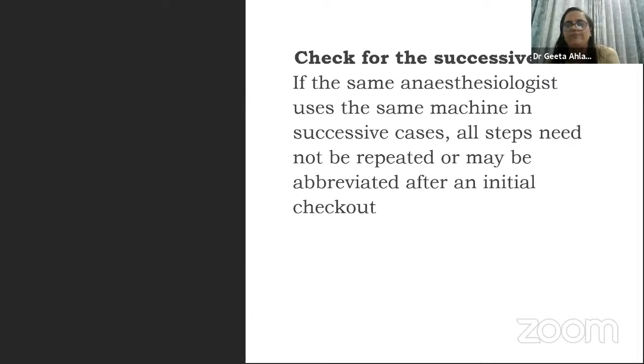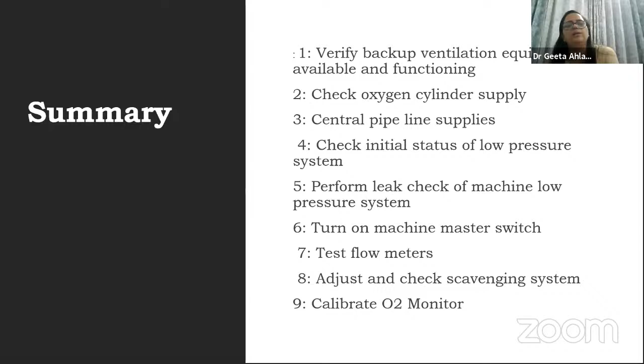Just to summarize, please verify your backup ventilation equipment. It should be available and functioning. Check all your supplies, check the initial status, check all leak tests, all your switches, all your flow meters, scavenging systems, and calibrate all your monitors. Safety is prime, safety saves us, but a small reminder to all: all this is useful like a parachute. A parachute is useful only if it is open. If you jump with a closed parachute, it is as good as jumping without it. So please, all these machines and equipment are only useful if you abide by the safety guidelines, follow the checklists, and then use them.